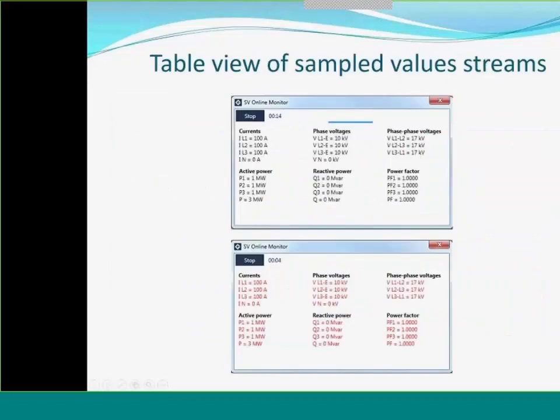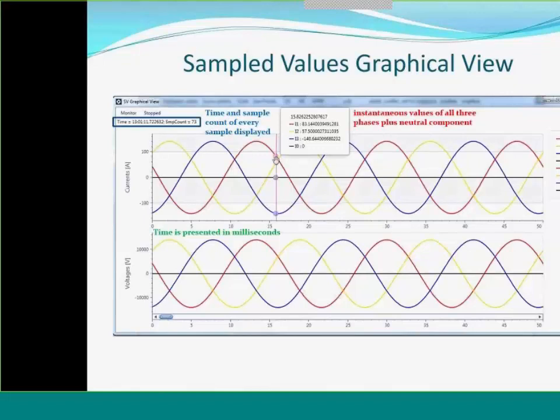Okay, and I'll just add, Nebojša, can you go just back to the next slide? So this particular calculation is done at the graphical user interface program. So it's a part of the Windows program. The gooseAir will feed process bus values to the user, and then the user on their own PC will calculate and present information in this view. So this is not part of the gooseAir program on the PC box. On the PC box, gooseAir will capture and forward or simulate sample values, but will not provide calculation for these windows. Yeah, got it. That's why it's limited to five seconds and whatnot.